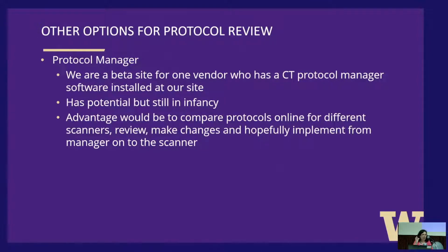And I think, Sam, you mentioned things like teamplay, but I don't know if they do protocol review for Siemens. But I think this is becoming common. I know GE has it. I don't know if any other vendors have protocol management. Philips does too. Because this is such a tedious process, vendors are looking for efficiency. So the advantage of doing this would be to compare protocols online for different scanners. You can review, you can make changes, and hopefully implement from the CT protocol manager straight on to the scanner, which would be fantastic.